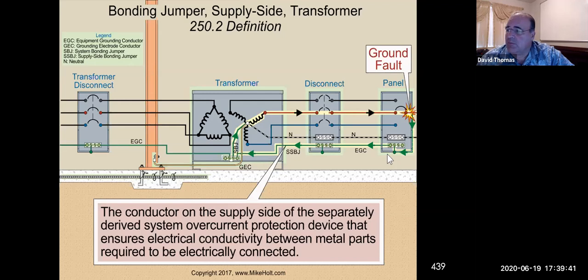For example, we have a ground fault. We're still looking at the supply side, but this is what happens with the transformer. Any ground fault, not short circuit, ground fault, where a hot touches the ground, the electrons will get carried back to the source through the equipment ground, but also through that supply side bonding jumper right in here. Where I'm talking about is right here. We'll take it back to the source, and that's what I was talking about.